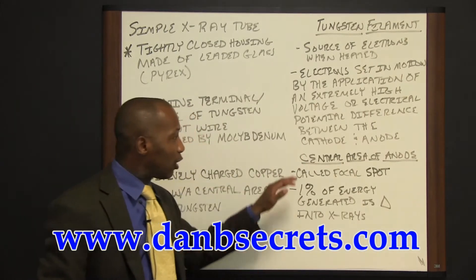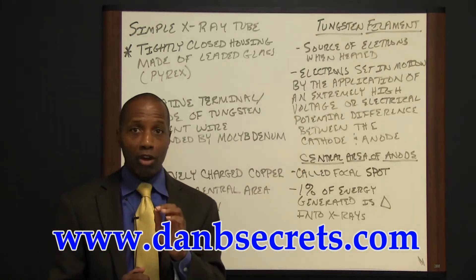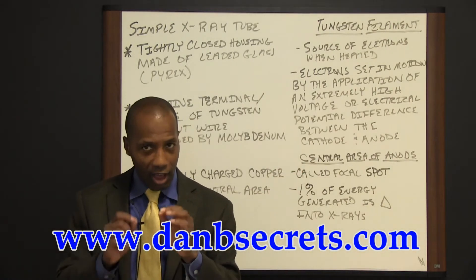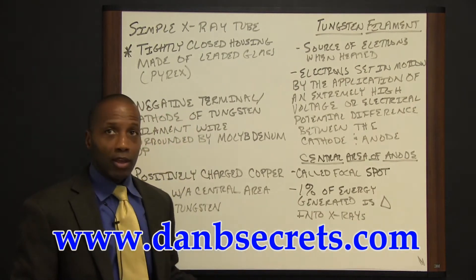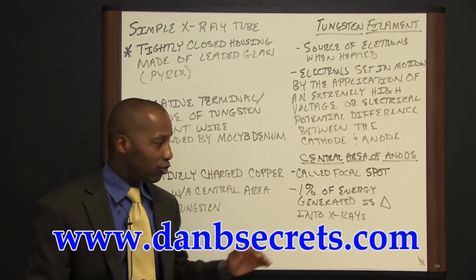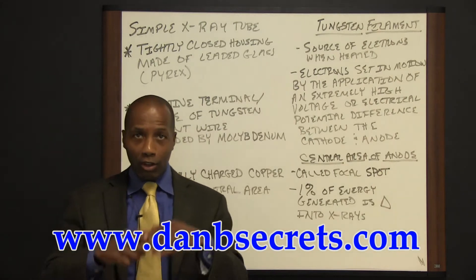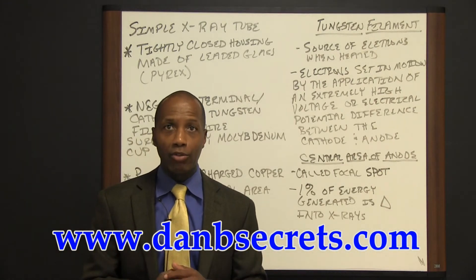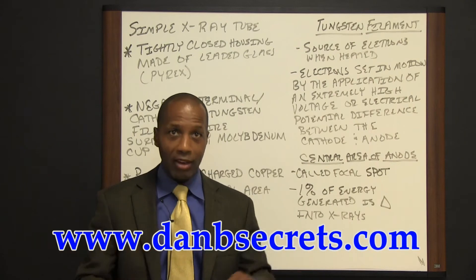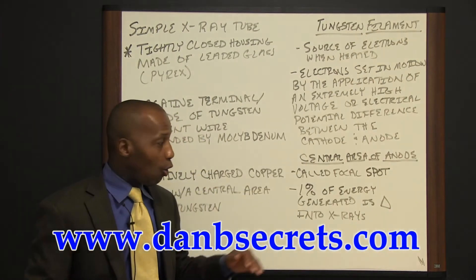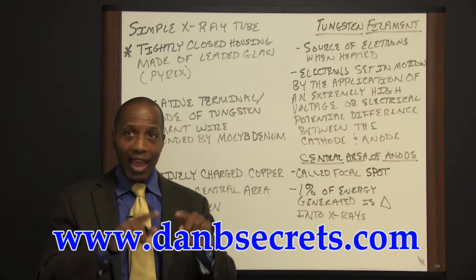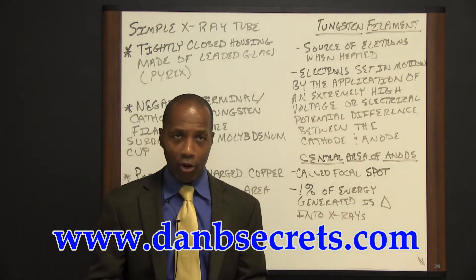The central area of the anode is called the focal spot. At the focal spot, usually about one percent of the energy generated is changed into x-rays, with the remainder dissipated as heat production or infrared radiation in the outer portions of the anode.